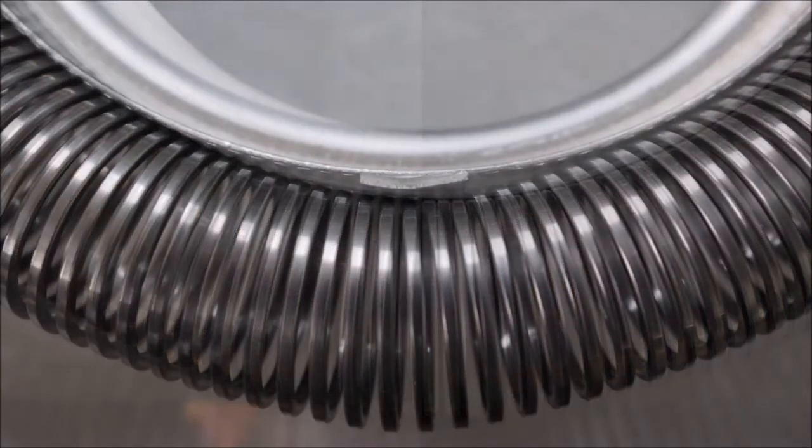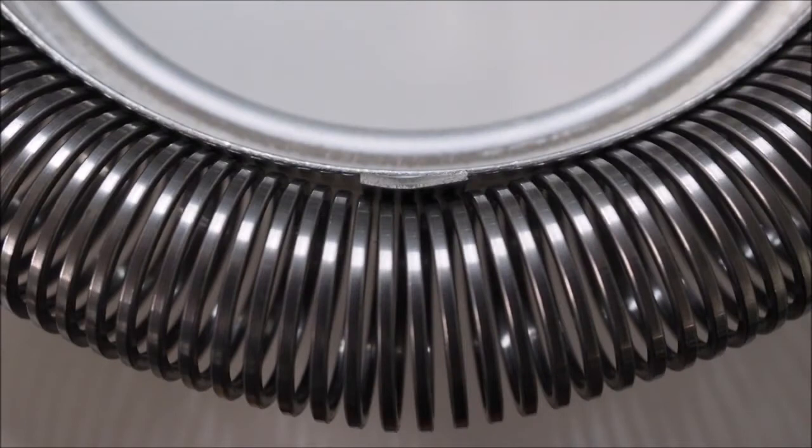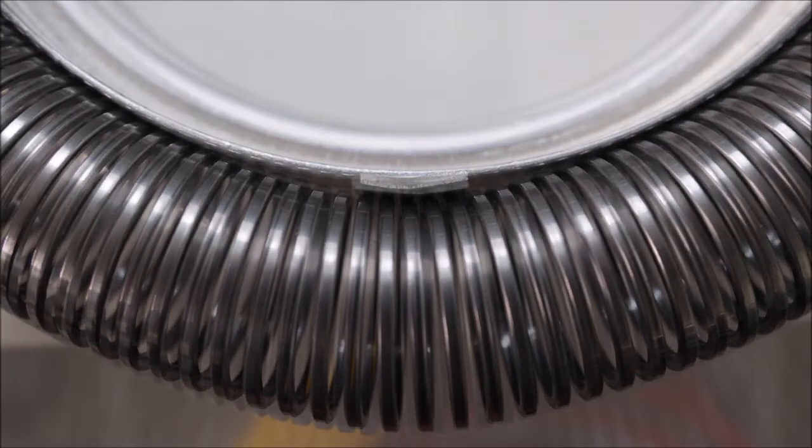As you can imagine, you have a weld, although this is a simulated situation just to show. You can see the gap either side of the weld there. That area won't be tested. The simple reason that the gap is too large. If you have high enough voltage setting, you're going to get some testing there. But otherwise, that area will remain untested.